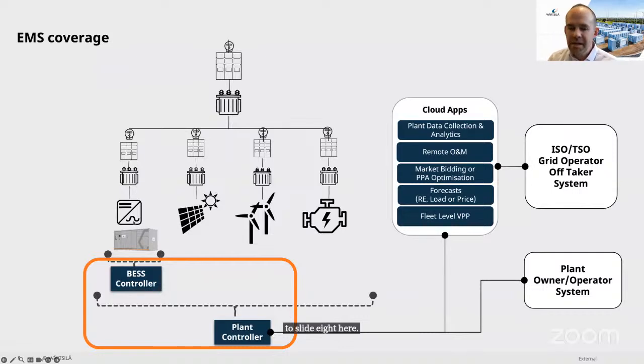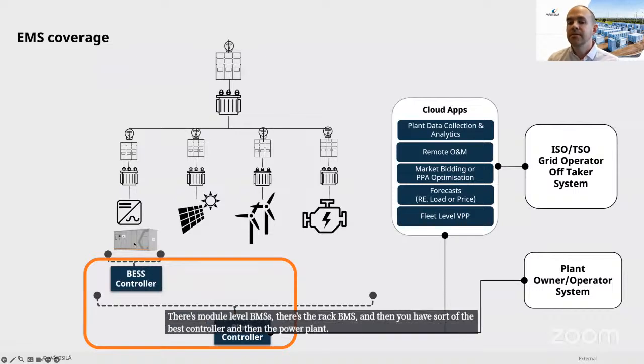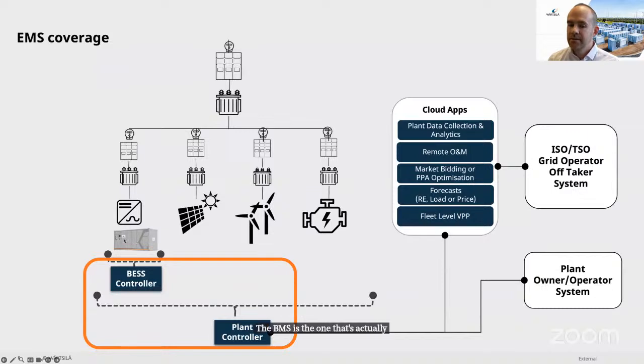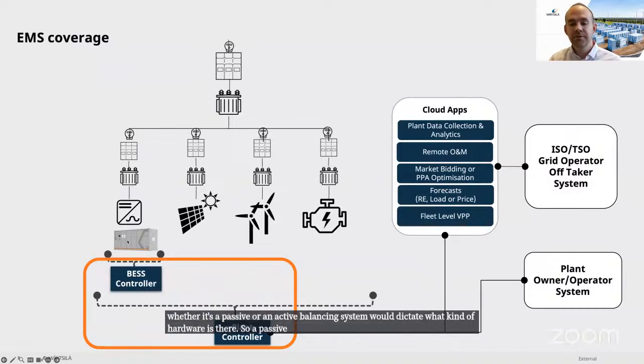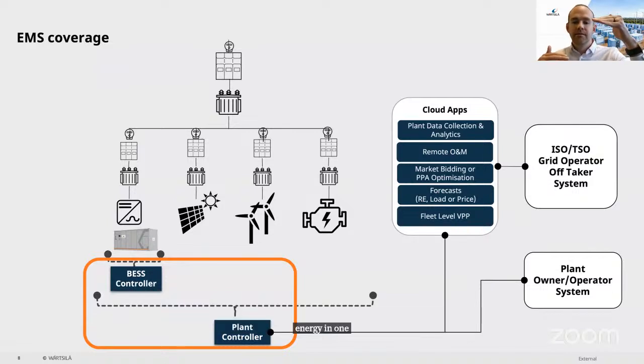We don't depict the BMS on this slide, but there's a BMS on it. There's module level BMSs, there's the rack BMS, and then you have the BESS controller and then the power plant. The BMS is the one that's actually doing the balancing, and whether it's a passive or an active balancing system would dictate what kind of hardware is there. So a passive balancer is a resistor, so you're bleeding off extra energy in one set of cells to bring them into alignment with the others.